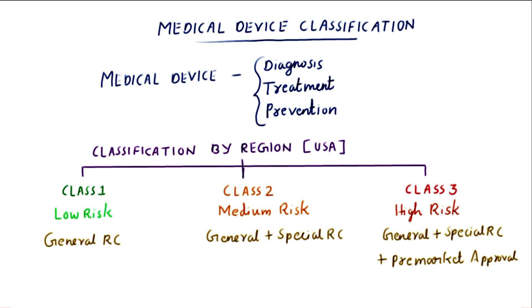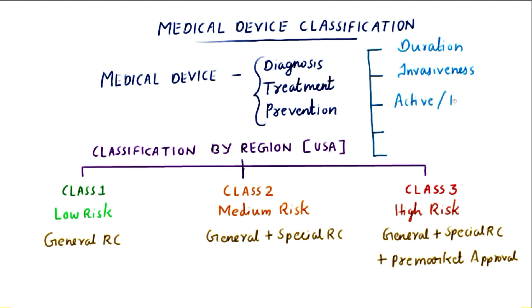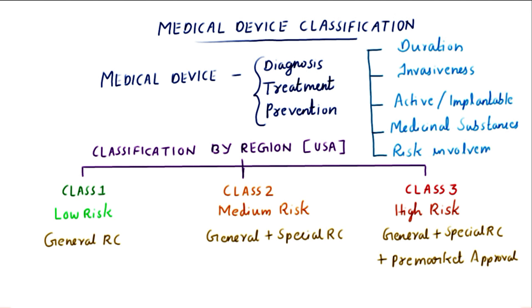There are certain parameters considered before classifying a medical device by FDA. The first one is duration — the length of time the device is used in the patient. The second is invasiveness — whether the device is surgically invasive or not. Third is whether the device is active or surgically implantable; active devices require external power to operate. The fourth is whether the device contains medicinal substances, and the last one is the risk involved when it is used in the patient.